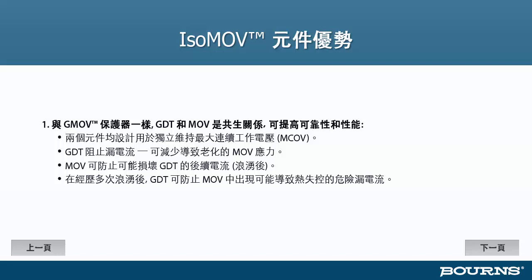So the GDT switches off the leakage current through the MOV, which eliminates a key source of the aging. The MOV returns the favor by preventing the follow-on current that would flow from the power line through the GDT after a lightning surge. If the MOV were not there, the GDT would quickly be destroyed by the power line current after it was triggered on by a surge event. So the MOV's job is to save the GDT. The GDT's job is to save the MOV, and they work together just beautifully over their life.